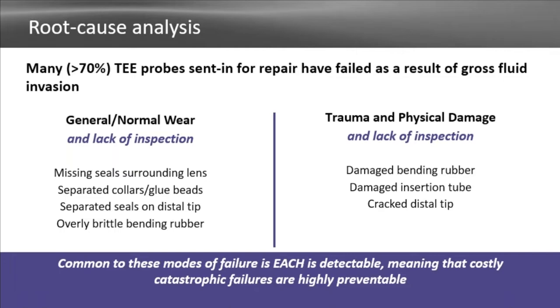We get so many probes in where that control housing has been submerged, and that catastrophically damages the probe. When we get those in, we have this giant industrial convection oven, and we have to open up the probe and put it in the oven to dry out for a couple of days before we troubleshoot, because there's sensitive electronics in here, here, and also in the scan head. Fluid and electricity equals things blowing up, so we have to dry them out before we test them, because if we test them while wet, we're gonna smoke the whole probe if it's not smoked already.